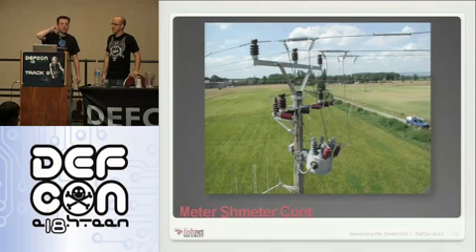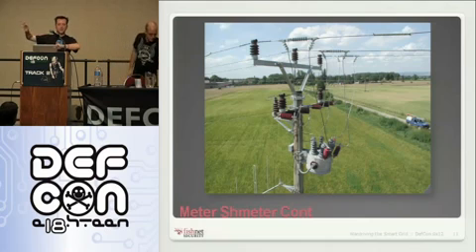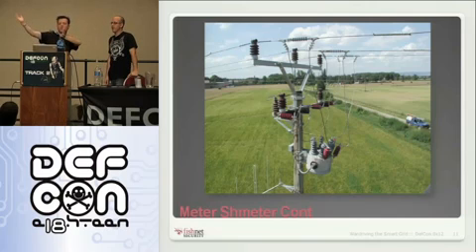And just another example. That's a recloser. So these devices usually have, say, modems or GPRS or something hanging off them now. These are essentially circuit breakers. So when your load changes, or you have an outage, say a lightning strike or something else, this is going to essentially just flip a really big breaker, okay? And it's going to move power one direction or the other.